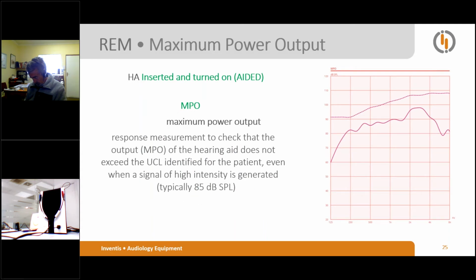Maximum power output. A properly functioning hearing aid should not only be able to amplify the external signals, but it must be set so that the amplification provided is not dangerous or annoying for the patient. In MPO, maximum power output mode, the instrument can provide a response measurement to check that the output from the hearing aid does not exceed the uncomfortable loudness level, UCL, identified for the patient, even when a signal of high intensity, typically 85 dB SPL, is generated.